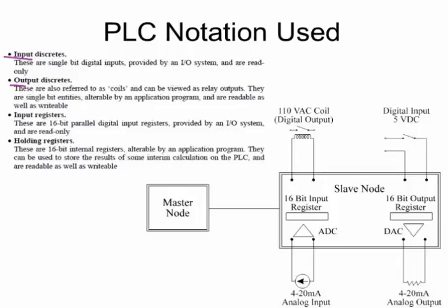Likewise, you get an output register. Exactly the same, it's for driving outputs if it's defined that way. Internally, reading the memory, that's what holding registers are about. That's where the PLC stores something in an integer file, does calcs on it, takes an input, scales it, does calcs on it, and sticks it in its memory. That's the holding register read function for Modbus. And again, you can write back to that, so you can write to the memory of the PLC. So these are the terms you'll see when we're pulling and pushing data to and from the slave devices.